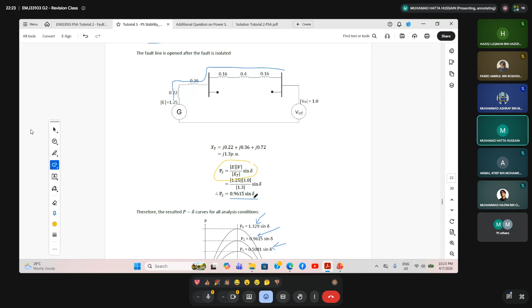To check this, I need to draw the power angle curve for all conditions - the sine waveform showing power on the y-axis and angle on the x-axis. My answer is correct because the pre-fault power is 1.329, during the fault it's 0.5081, and after isolating the fault it's 0.9615. So what I got is correct - the post-fault value should be in between.